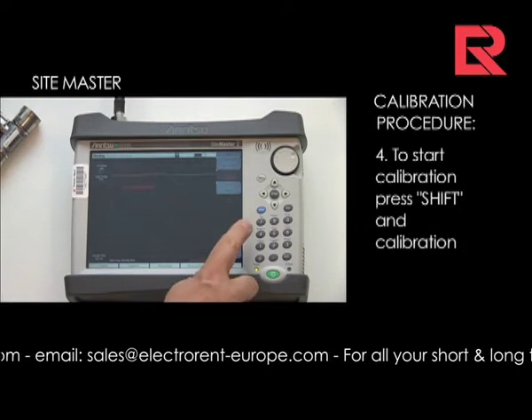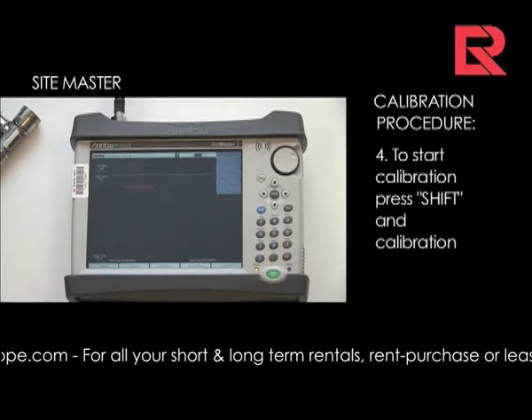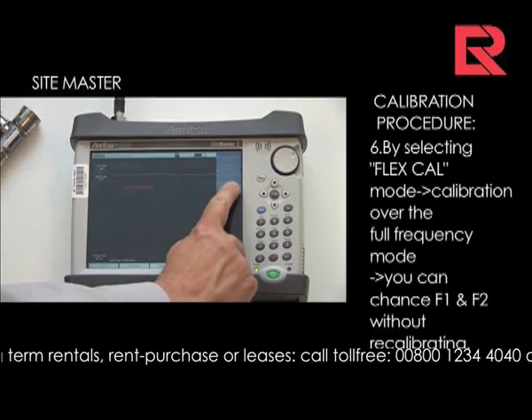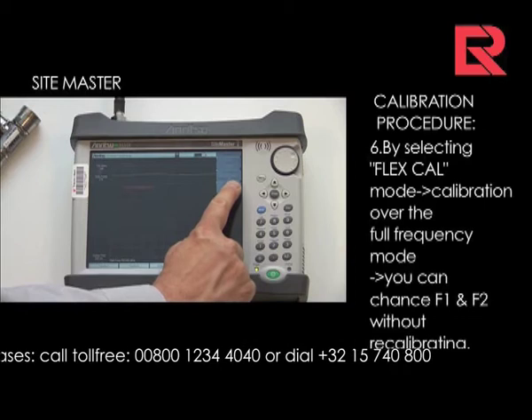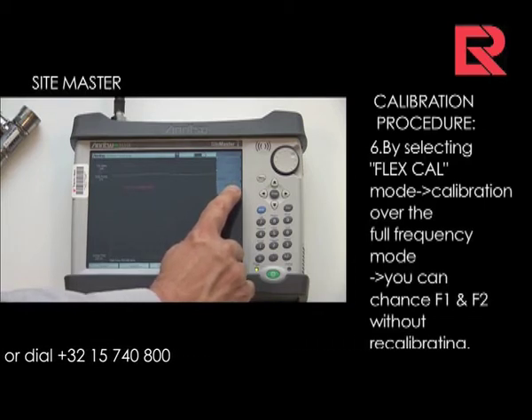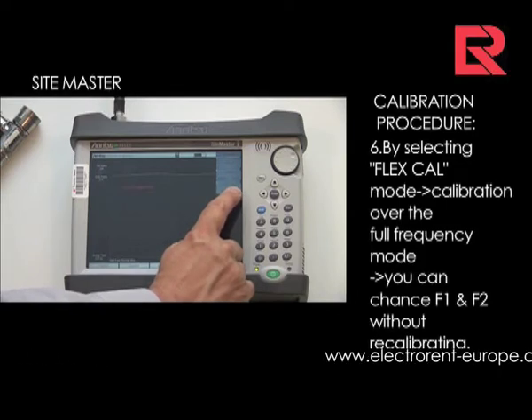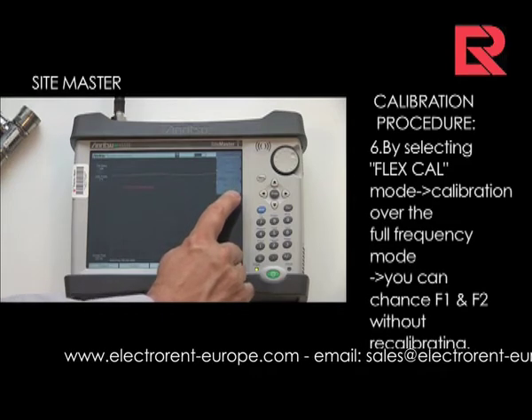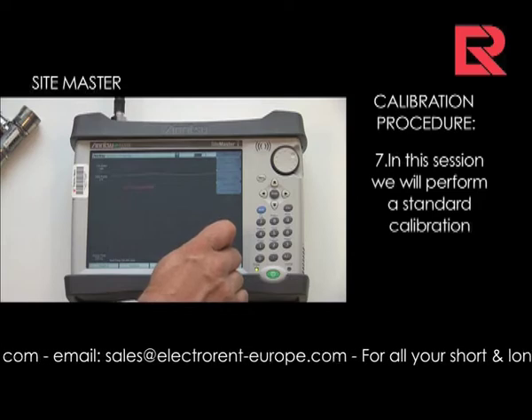To start the calibration you can use the shift calibration button. By selecting the FlexCal mode, your instrument will be calibrated on the full frequency range. This will allow you to change F1 and F2 at a later stage without the need of recalibrating. It will slightly degrade the readings but speed up the troubleshooting. In this session we will perform a standard calibration.